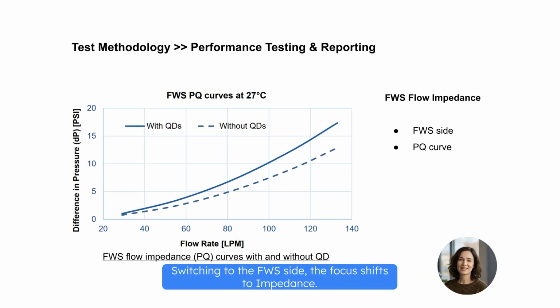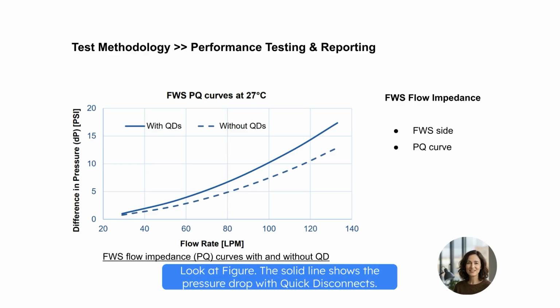Switching to the FWS side, the focus shifts to impedance. Remember, the CDU is a restriction in your loop. Your facility pumps must be powerful enough to push the required flow through this resistance. Look at the figure. The solid line shows the pressure drop with quick disconnects. That gap represents significant head loss. If you fail to account for this extra DP in your facility pump sizing, you will starve the CDU.